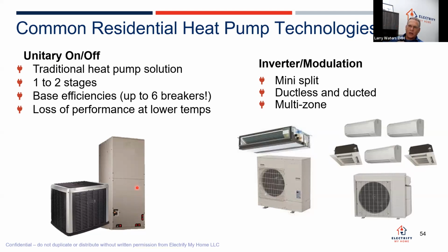So when it gets cold outside, it just speeds up. And a lot of times these things are fully operational at full capacity, all the way down below 17 degrees, sometimes all the way down to 5 degrees. So if it gets below 5 degrees in the Tri-County area down there, we have other problems we need to worry about. And if it gets below 5 degrees down there and your customer has any heat left in there, they're going to still be happy. So you're going to find these mostly in mini split technology, ductless like this, or ducted, and then they also have multi-zone.